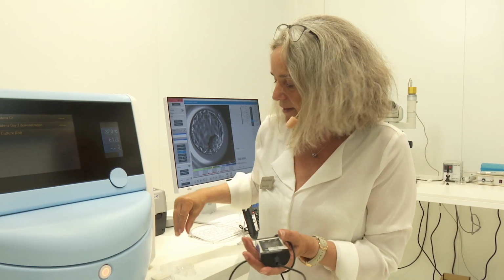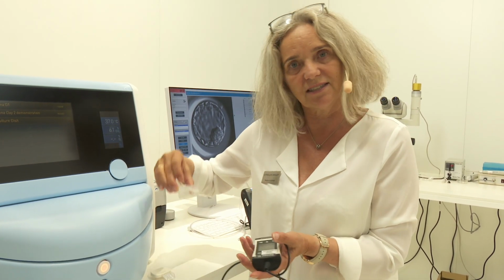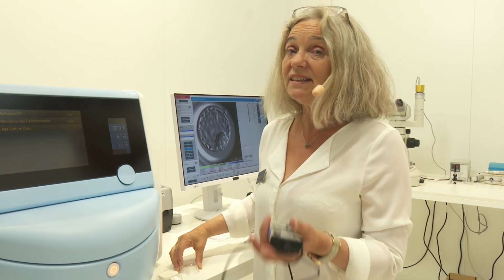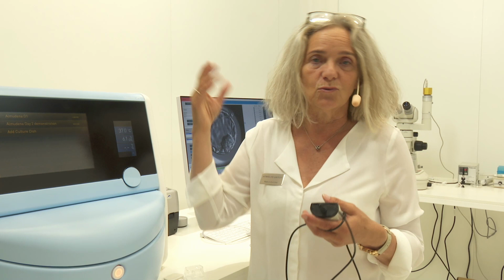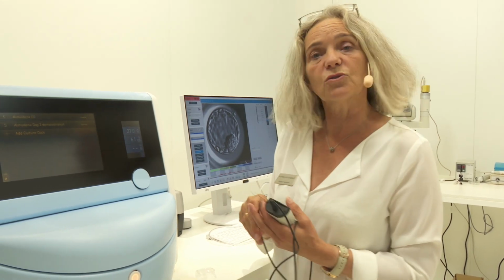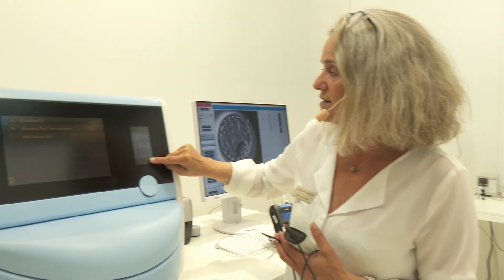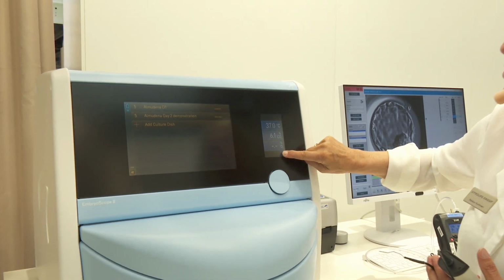sensors that work independently. It's just like a spiral in a sandwich construction under the plate where the embryo dishes are located. So in case one of them should have a malfunction, there will be a warning, and you will contact us at Vitrolife Support. But you can still continue to culture your embryos, because the other one will completely take over. So it's safe for you to do that. But you need to validate each of these 2 sensors. So again, you go into the tool here.